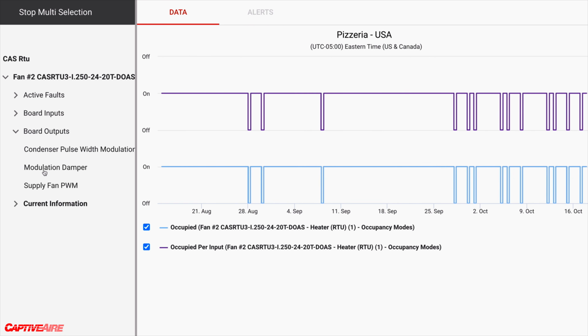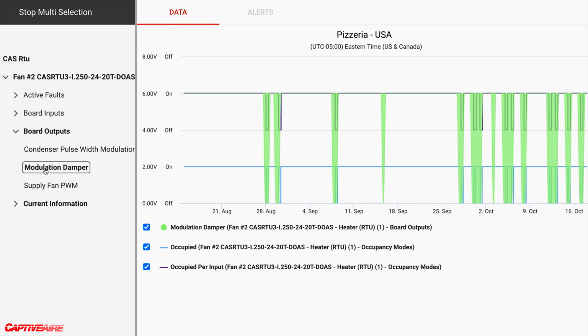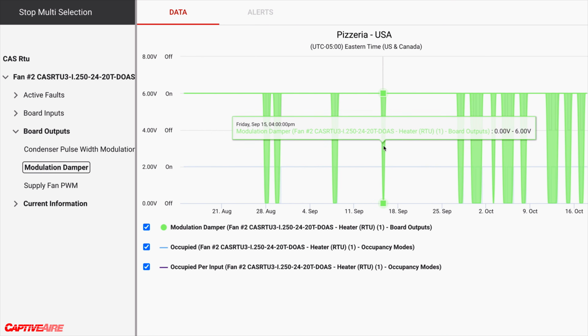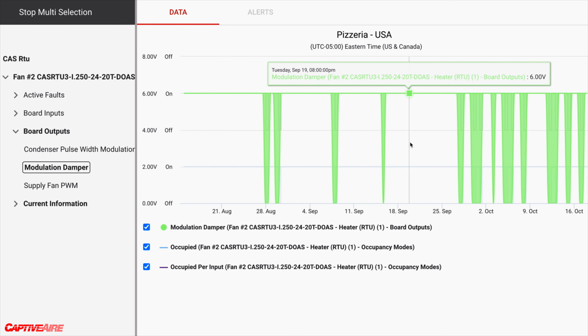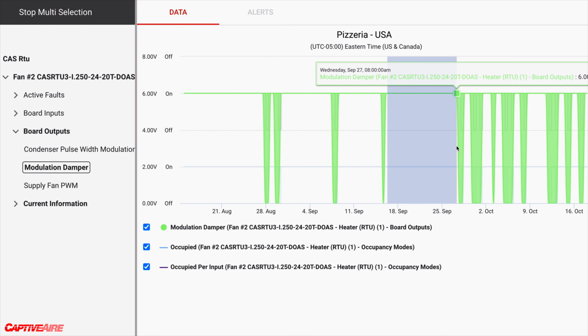If we pull up our damper, we can verify that this thing's going to be processing a lot more outside air, and it's also, while it's occupied, keeping that fan running continuously. That's going to be a lot of wasted energy just from the outside air portion, as well as wasted fan energy that they simply wouldn't need during these times. So that's going to be one big piece of it.